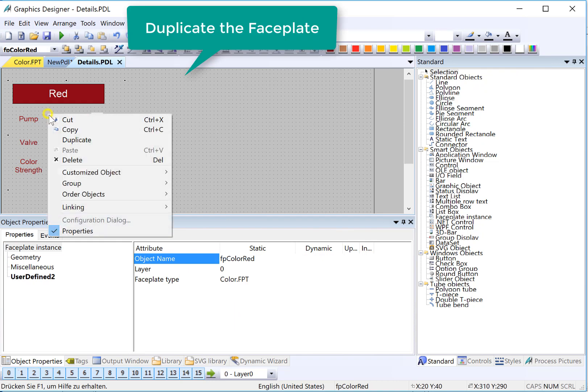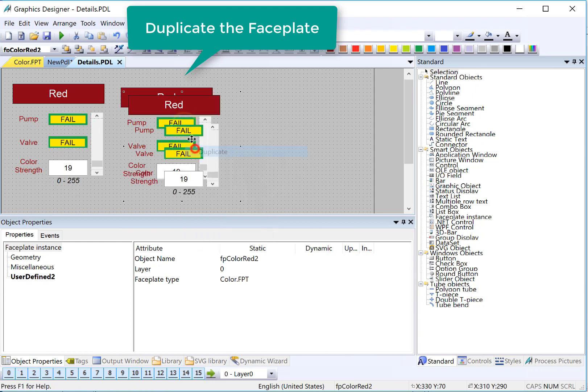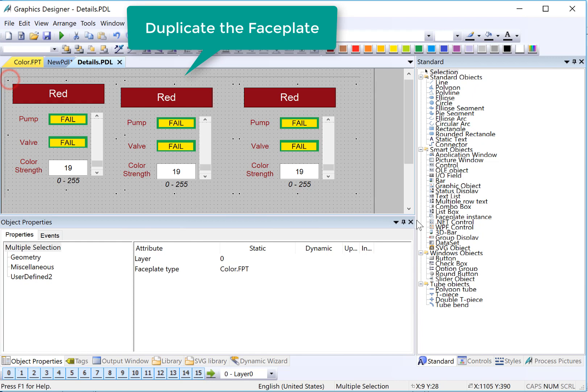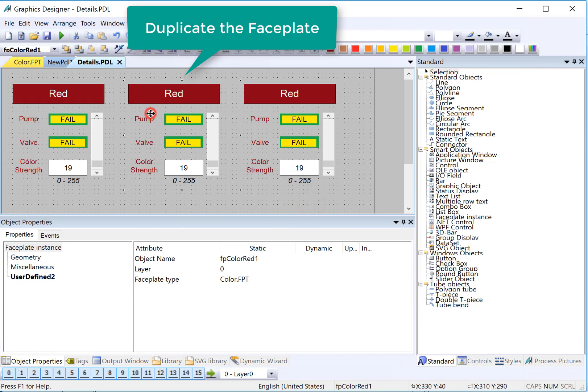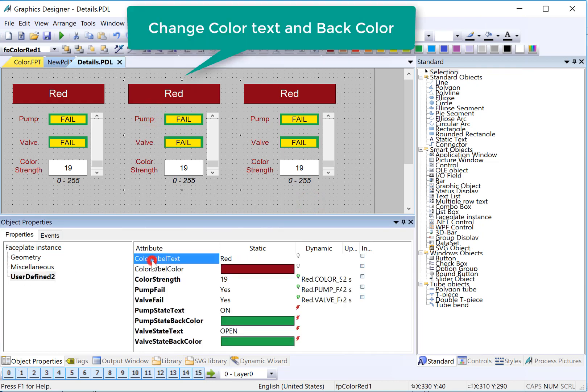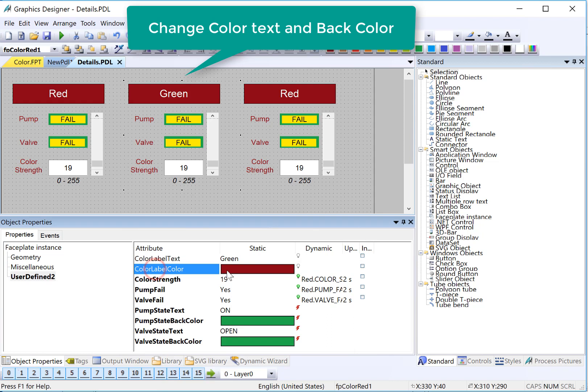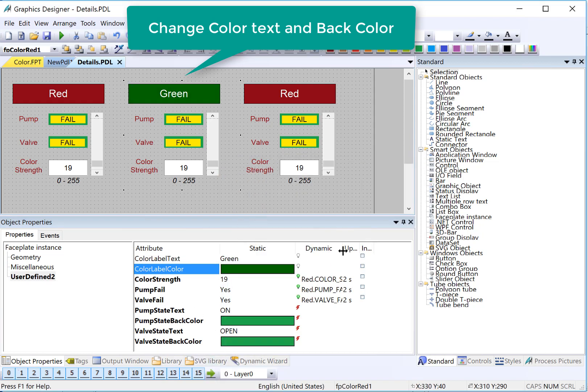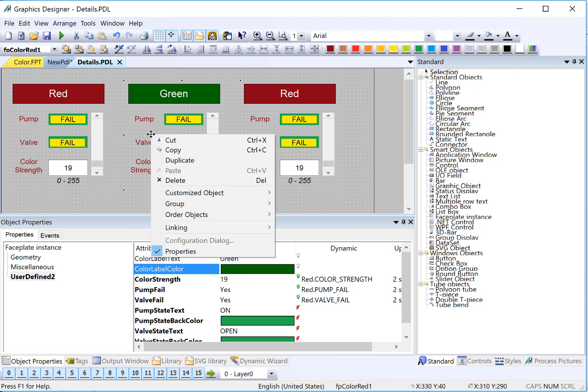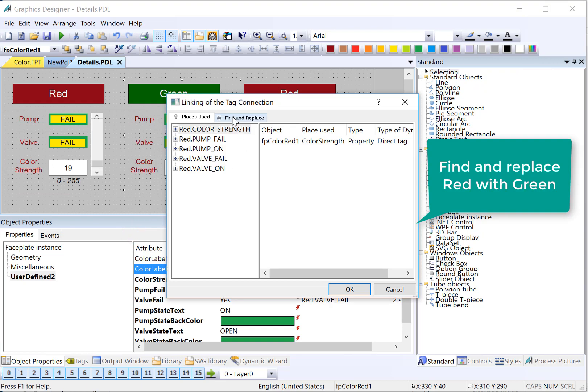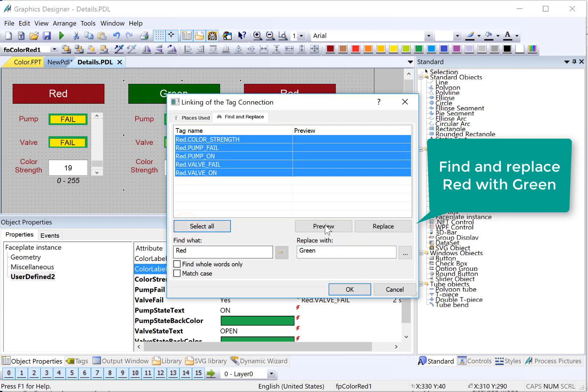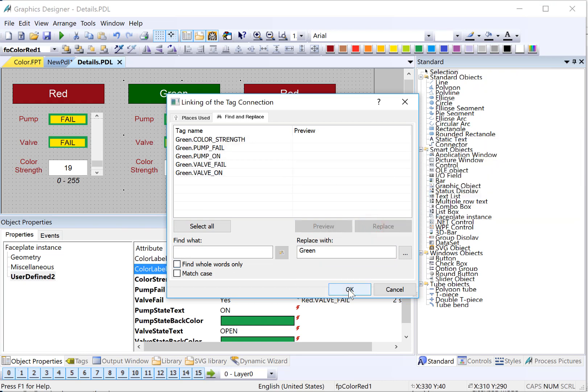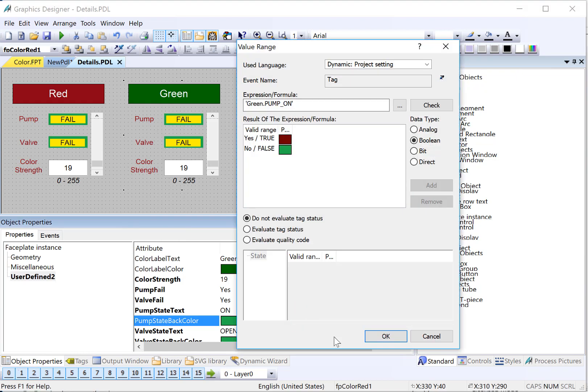Next, we can just duplicate this. And then I will lasso these objects, justify evenly space. For this one, our color label text is going to be green. And the color label color is also going to be green. Now, we'll need to change all the red instances to green instances. And we can do that with our linking dialog. So I'll right-click, linking, tag connection. I'll go to find and replace and say find red, replace with green. So we'll select, we'll preview, that looks good, and just hit replace. Now, if we look at this, all of our tags have been changed to green, even in the dynamic dialog.